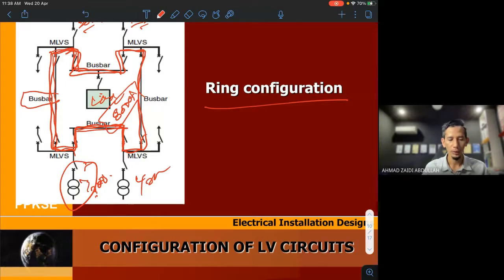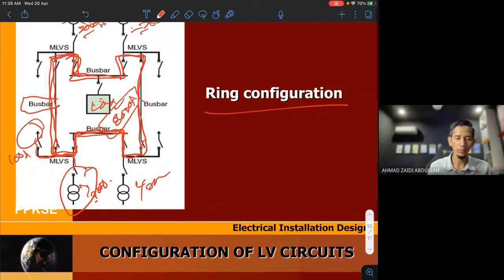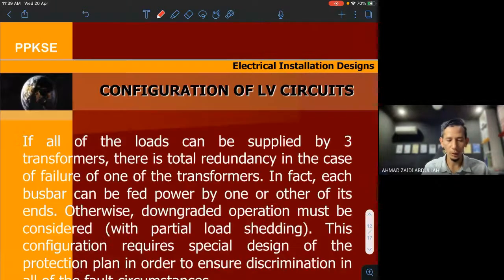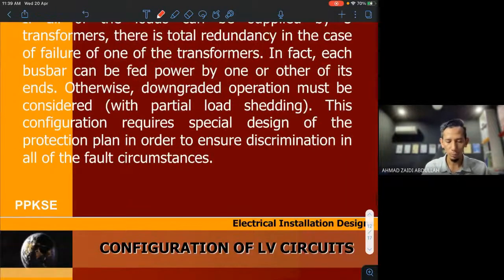maybe this one just covers this load, a very low load, let's say this load is 100 amp only. So the busbar was designed to cover 100 amp only, but sometimes when we design a ring circuit, this 2000 amp needs to transfer to this load, so this way must be capable of carrying 2000 amp. That is the issue that they are trying to explain here.